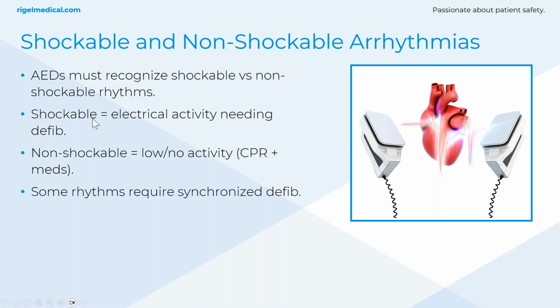So there's shockable, one that defibrillation can correct. There's non-shockable, and that means that there's no activity, or at least low activity. And then there are also some rhythms that require a synchronized defib, and that's when there are still pulses present, and there are ways that they assess the timing of those signals so they don't shock at the sensitive periods. If you shock at the wrong time during that sensitive period, called the repolarization phase, that can actually lead to fibrillation, so it has a negative effect. Some of the diagrams explain that a little bit better.